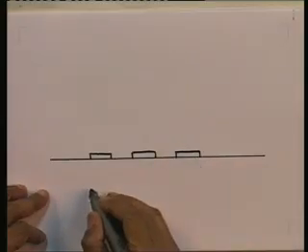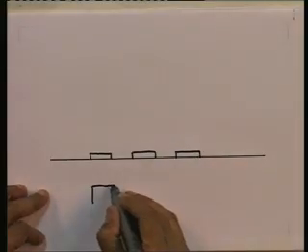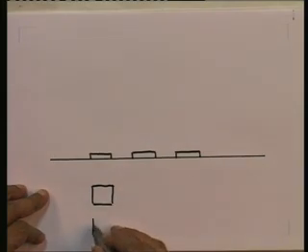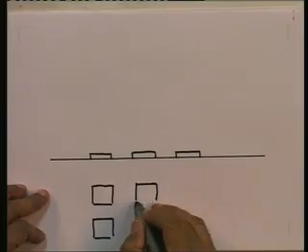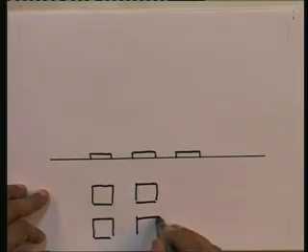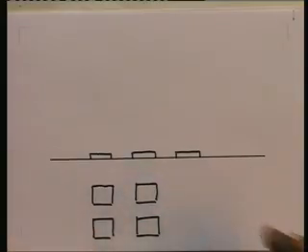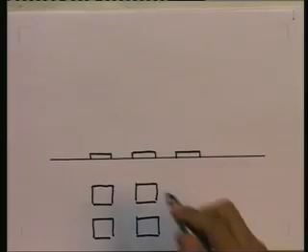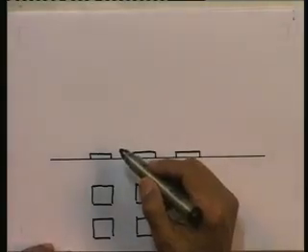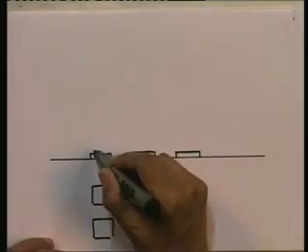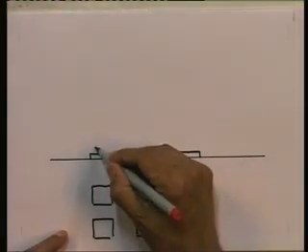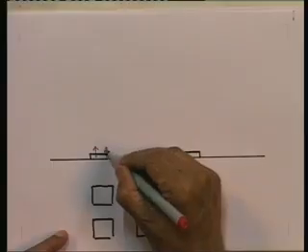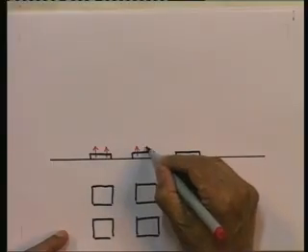If I had a plan view, actually there may be an array like this, 1 would be like this in the plan view, 2 like this, and so on. So, it could be a rectangular array of chips. Typically, each of these may be, let us say, a centimeter by maybe a millimeter high, and within it they have all the electronics that we are talking about. Now, a requirement would be the heat that is being generated from these chips would be flowing out like this. This is how the heat is flowing, shown by the red arrows.